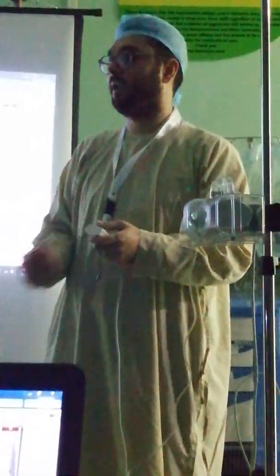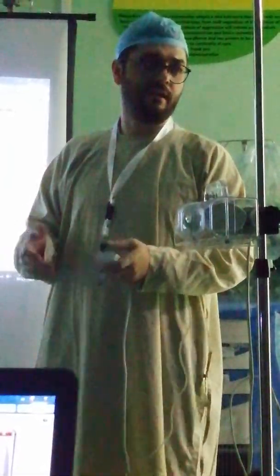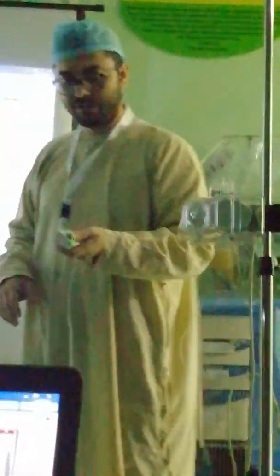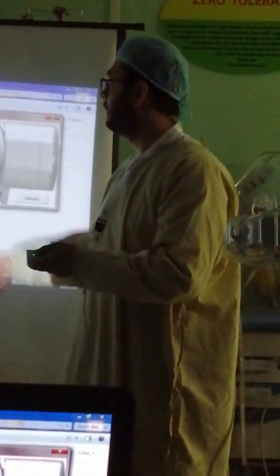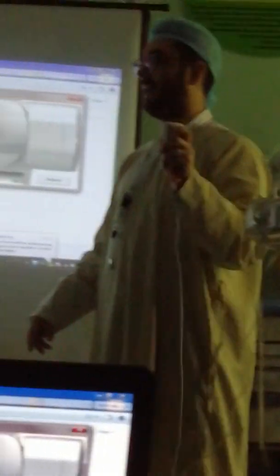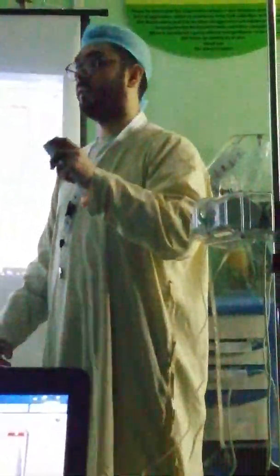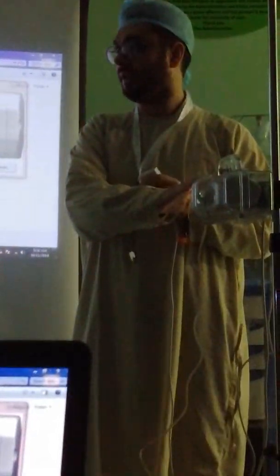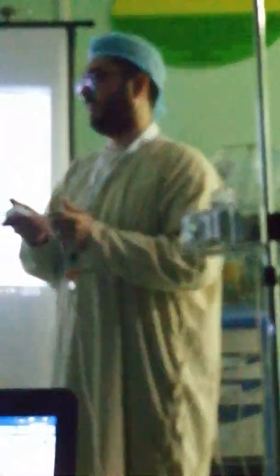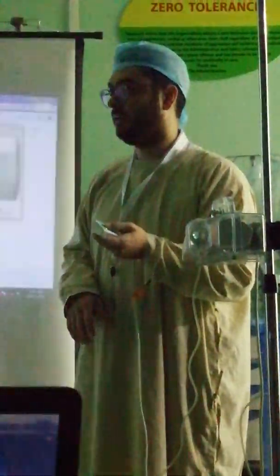This whole concept starts with getting the patient into the therapy and making nurses less busy with pain management — patients can manage their pain themselves rather than ringing the bell every time they feel pain, which would require a nurse to be there 24 hours. So if the patient feels pain, they press the button. Look at the screen — now the patient receives their first bolus dose. After ten minutes only can they receive the next one. Whatever times they press in between, they will not receive anything — but how many times they press will help us assess the patient.